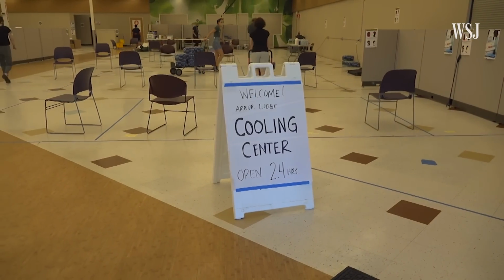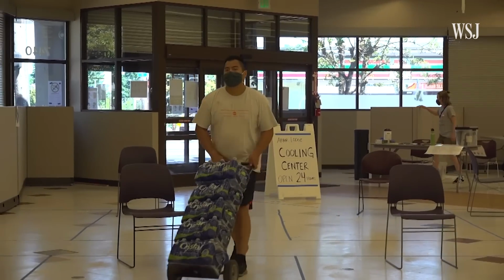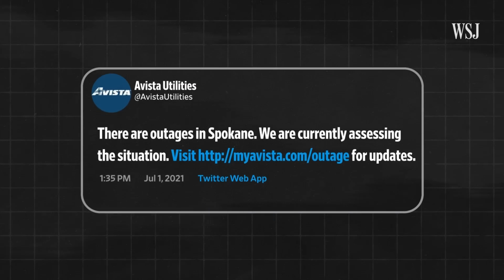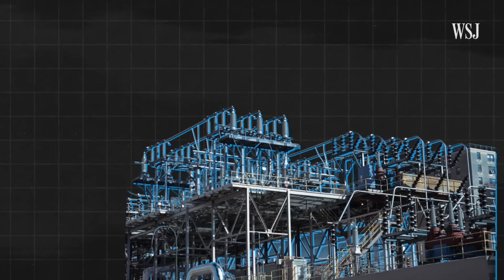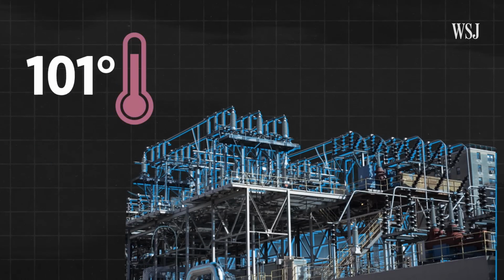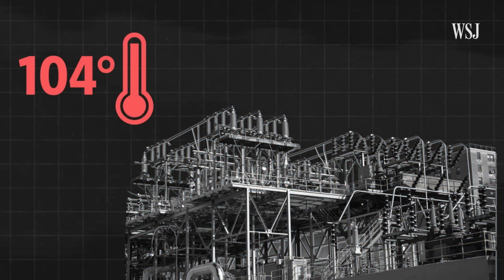That happened last year in the Pacific Northwest when heat hit the region. All-time record heat crippled the Pacific Northwest, an area where most residents live without air conditioning. In Spokane, Washington, heat forced the local electric utility to turn off substation transformers, which can't function at temperatures higher than 104 degrees. Blackouts lasted for a couple of days. They turned off the equipment so that it wouldn't be severely damaged.